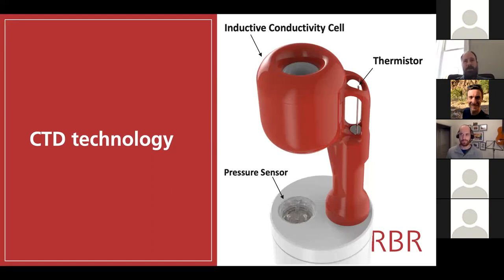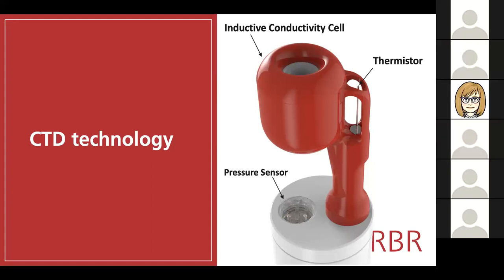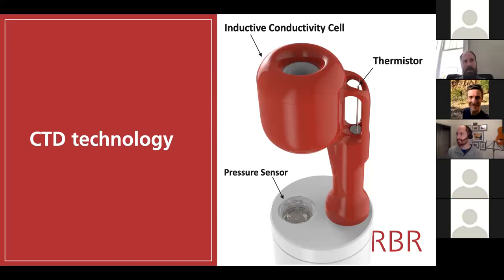Typically with an electrode-based cell, you have problems of polarization of the electrodes. And so rather than doing it in a DC sense, where one electrode is always more positive than the other, you actually apply an alternating current signal, an AC signal, and make those measurements multiple times back and forth. Now, we'll talk a little bit more about the pluses and minuses of that in a second.